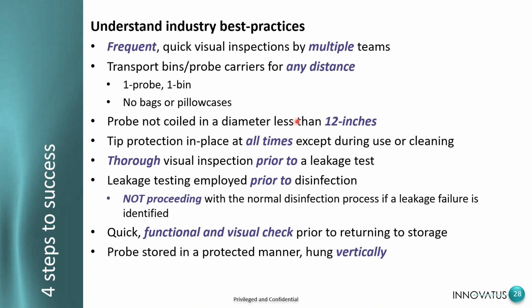And if you kink that, there is a metal mesh, kind of looks like a stent if somebody's getting a stent put in. And once you kink that, you really can't unkink it. You really got to tear it. I've seen organizations where they'll try and re-round that insertion tube. It doesn't work very well. To do it properly, you have to tear apart that probe and replace that metal mesh. So we don't want to coil it any less than 12 inches in diameter.